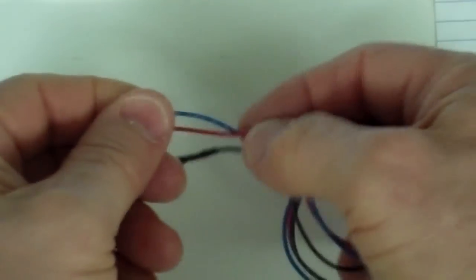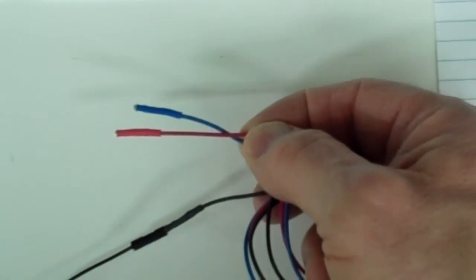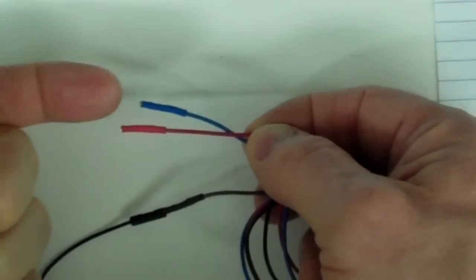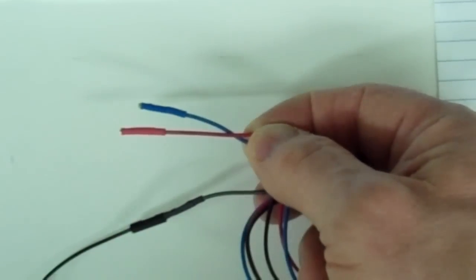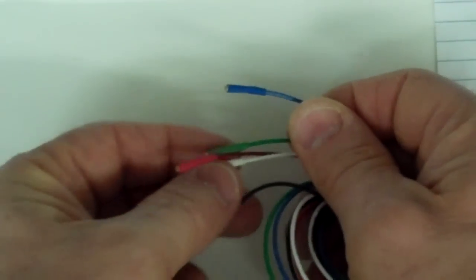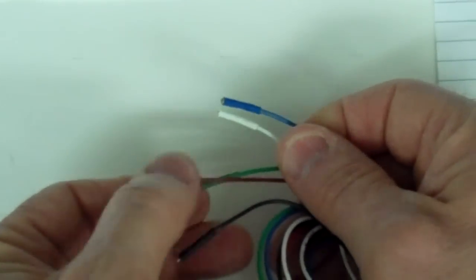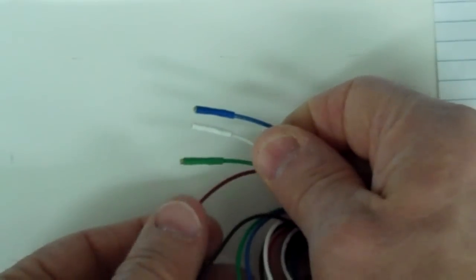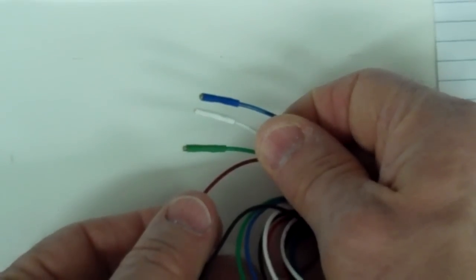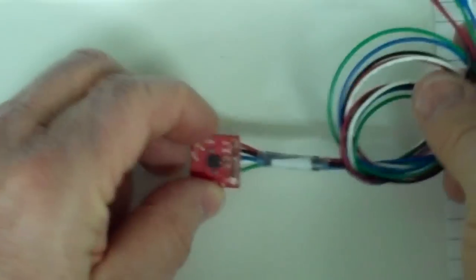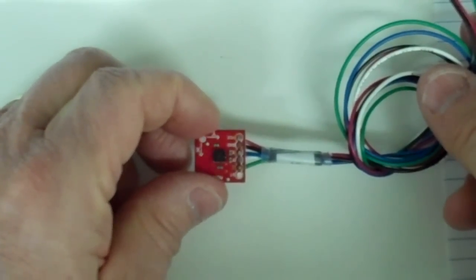The consistent color coding also used beyond the first 3 that I have mentioned would be blue, which is the output of the sensor. And in the case of more than one sensor output, we would follow the other color codes, which would be blue, and then white, and then green. So these 3 would be 3 outputs which happen to come from the accelerometer.